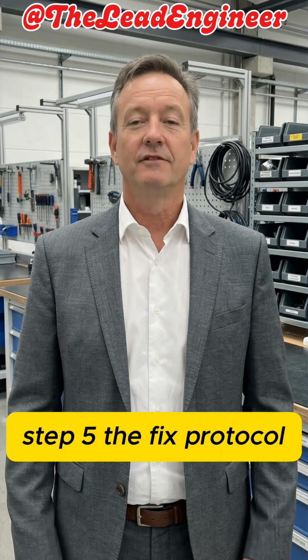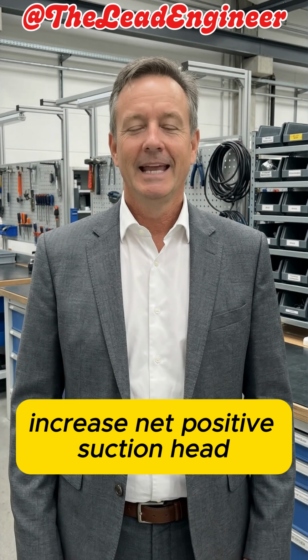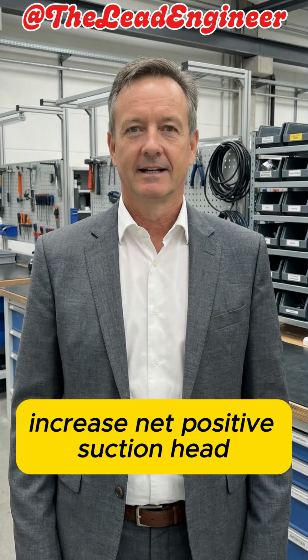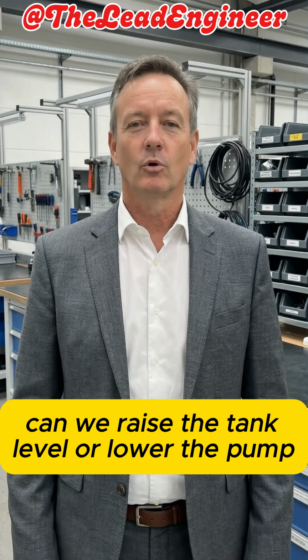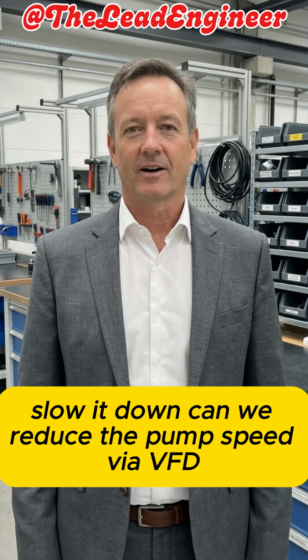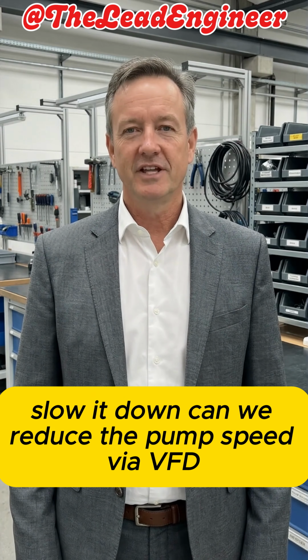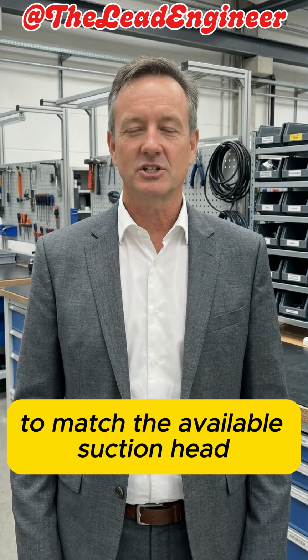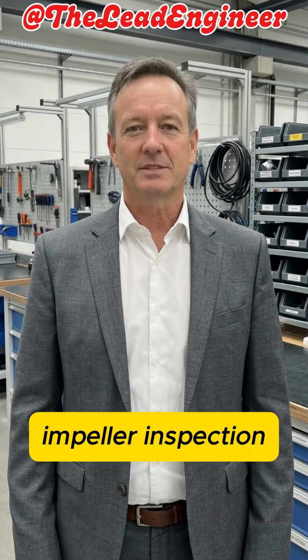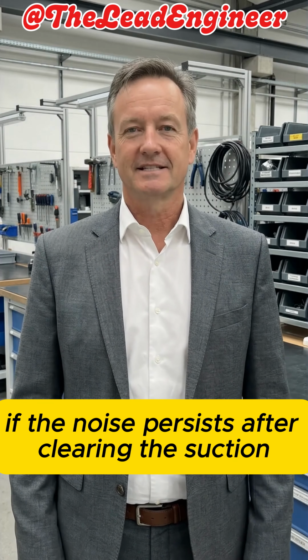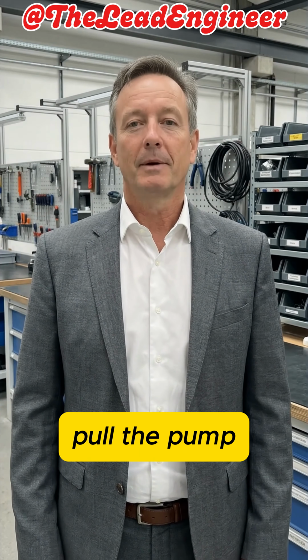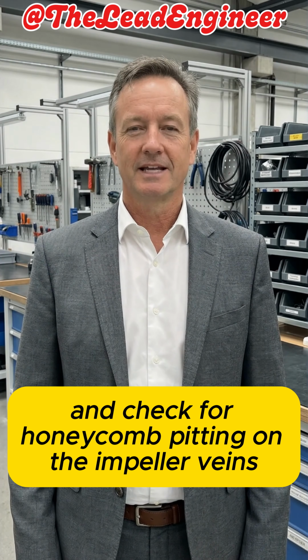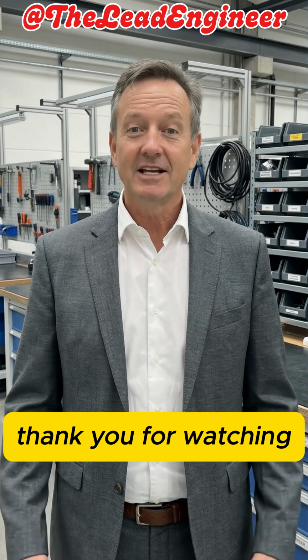Step 5. The fix protocol. Increase net positive suction head. Can we raise the tank level or lower the pump? Slow it down. Can we reduce the pump speed via VFD to match the available suction head? Impeller inspection. If the noise persists after clearing the suction, pull the pump and check for honeycomb pitting on the impeller vanes.